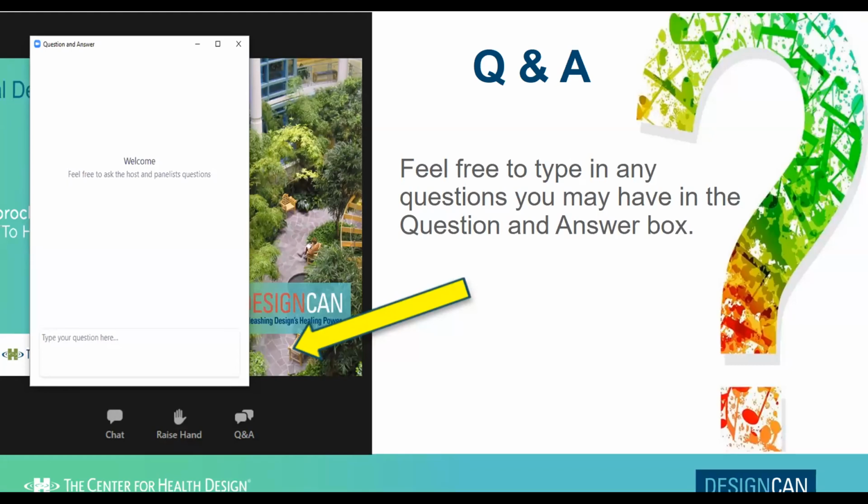So this is an interesting question. Is there any concern that if the room is designed to allow for procedural mode, then all other code requirements for MEP would be triggered and thus would burden the project cost? Have you encountered that argument? We didn't feel that there were any implications to the code, and that is because bedside procedures are performed today, whether it's a trach or a PICC, or a code blue, right? Those things are happening today operationally and are not addressed by code officials. So by adding more air changes and positive pressure, we stayed away from any code implications. We were only improving the space. So that was our approach.